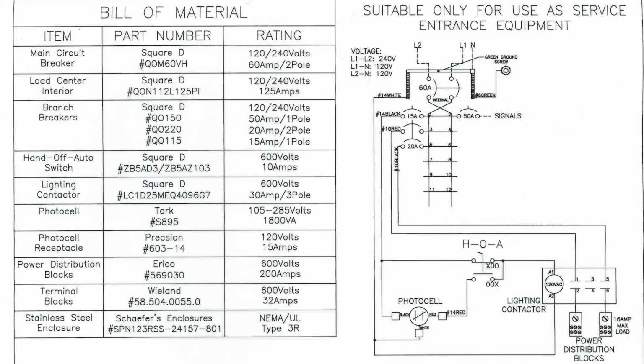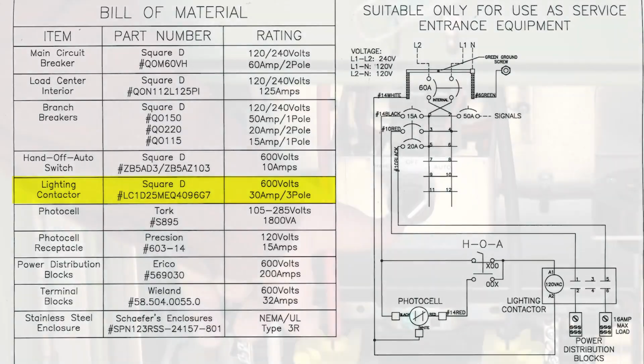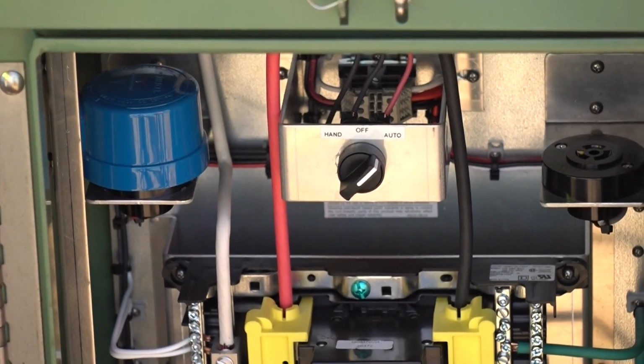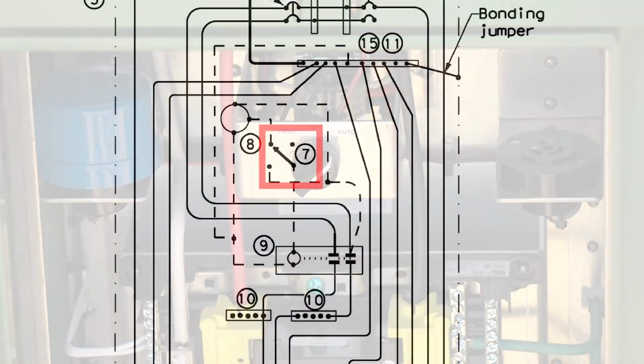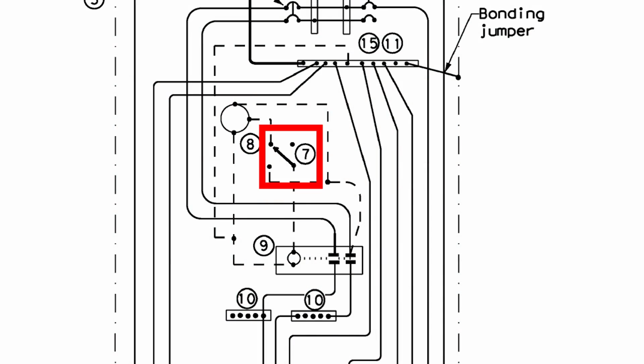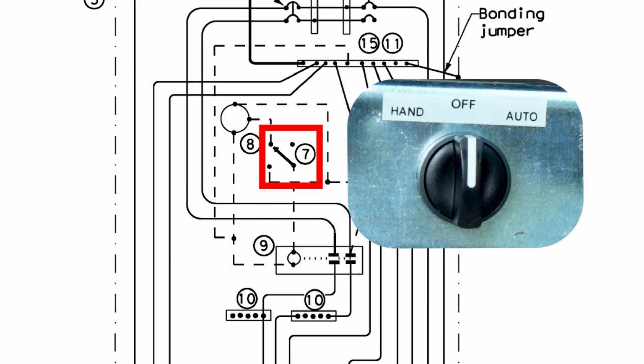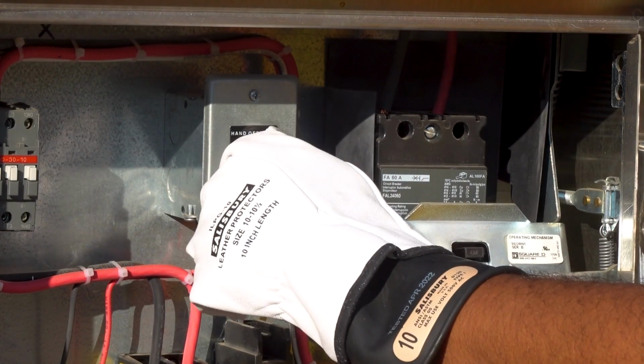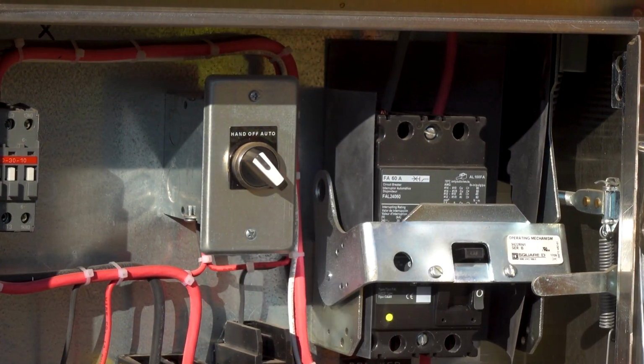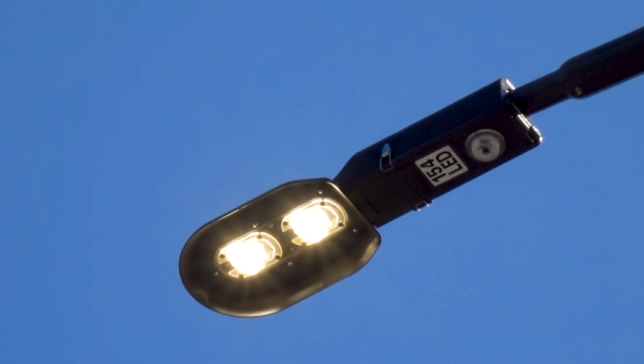The brand and model number for the contactor is on the unique line drawings sent with the enclosure by the UL 508 shop. Next, the inspector should inspect the handoff auto switch. The handoff auto switch controls both the manual and automatic nighttime operation of the lighting contactor. After electrical power has been turned on to the service, the inspector should place this switch in the hand position and confirm operation of all lights.